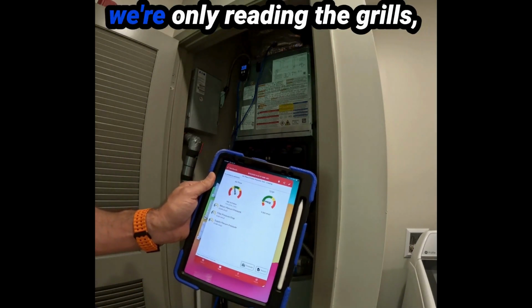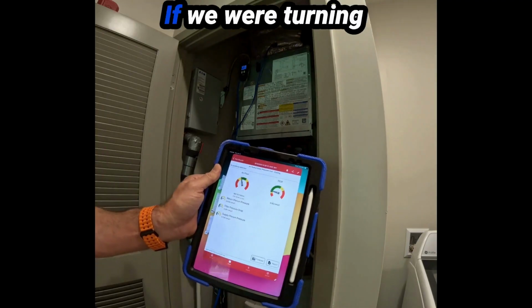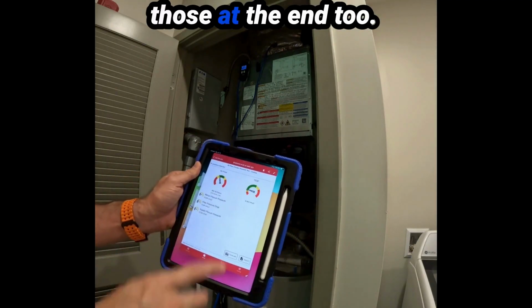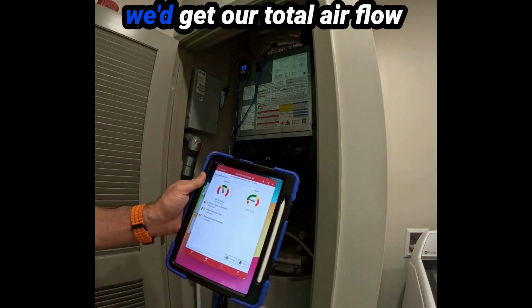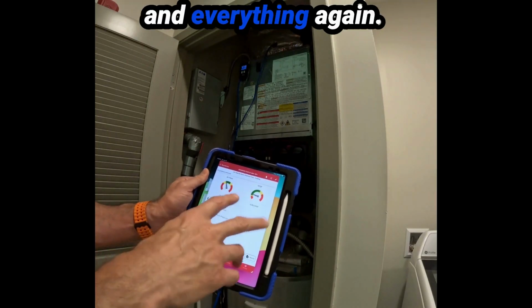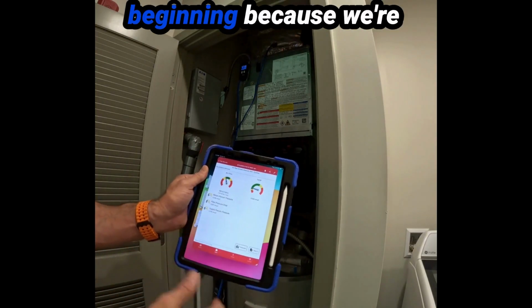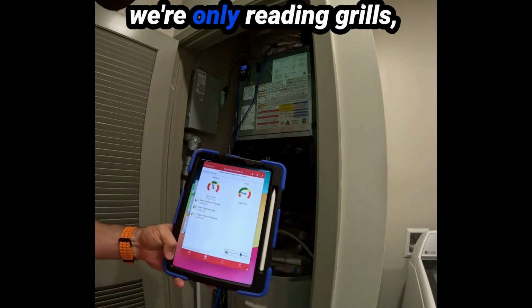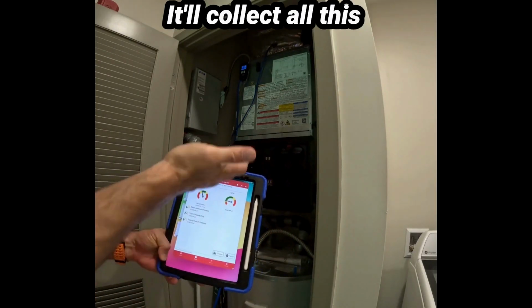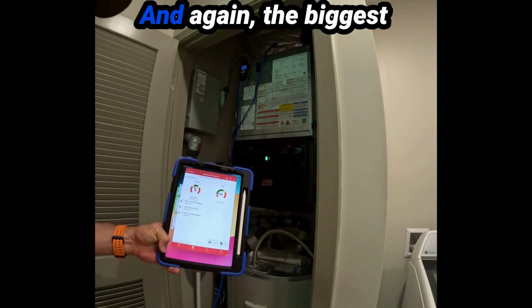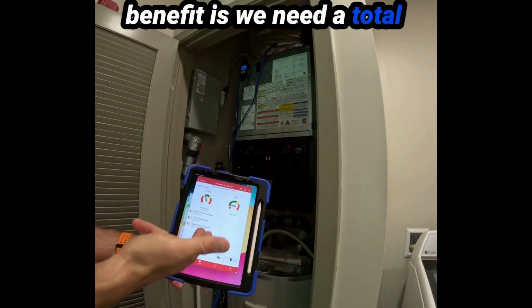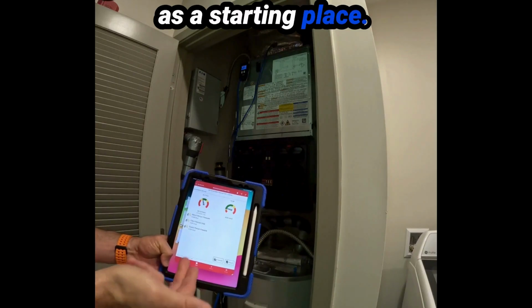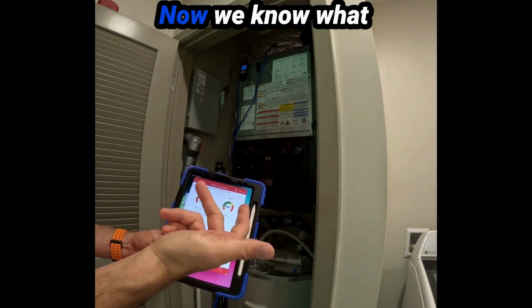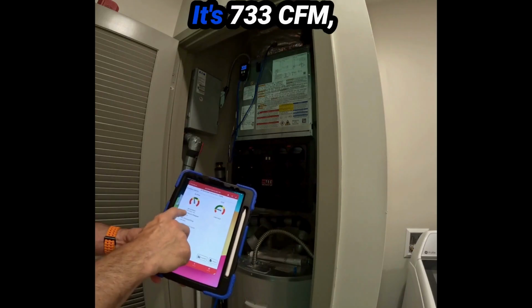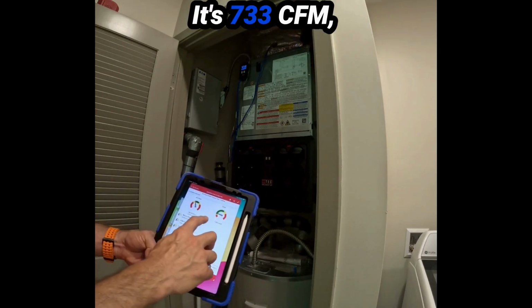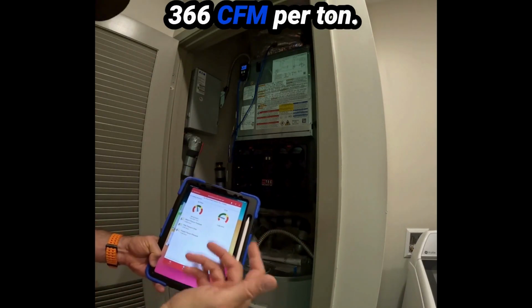In this, we're only reading the grills. We're not turning dampers. If we were turning dampers, we would need those at the end too. After we turn the dampers, we get our total airflow and everything again. But for this, in the beginning, because we're not turning dampers and we're only reading grills, it's perfectly acceptable to collect all this information right off the bat. And again, the biggest benefit is we need a total airflow in the beginning as a starting place. So we have that number now. We know what the total airflow is: 733 CFM, 366 CFM per ton.